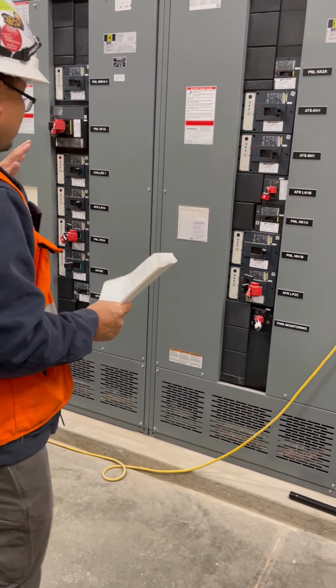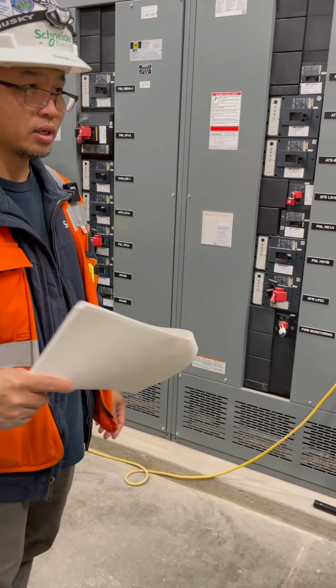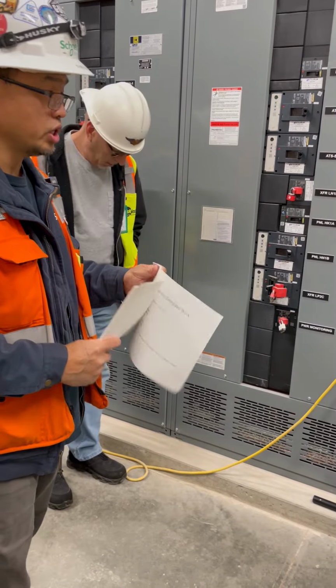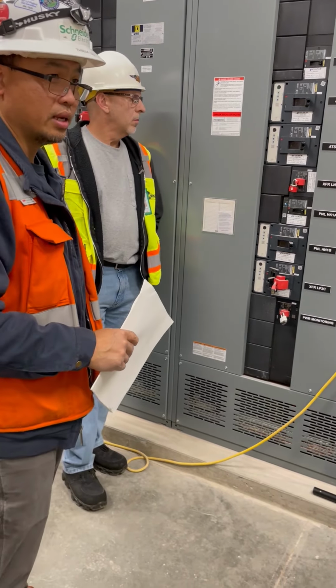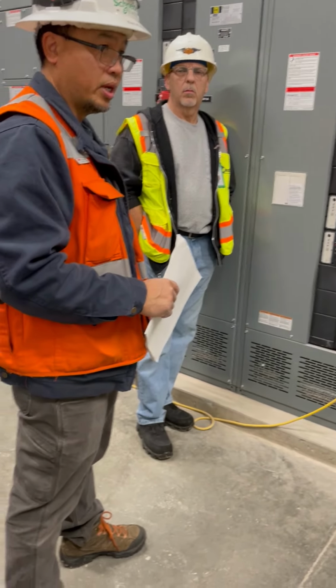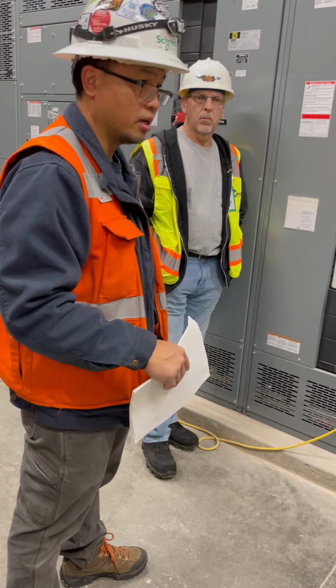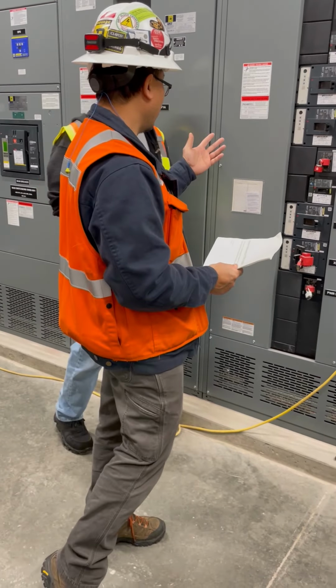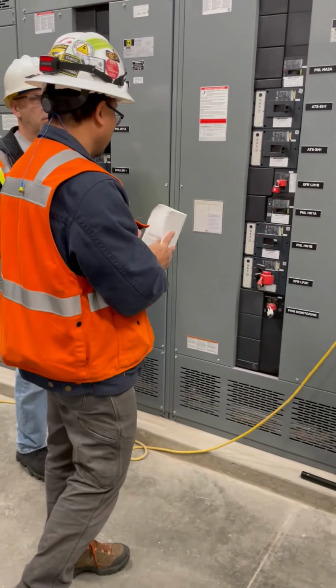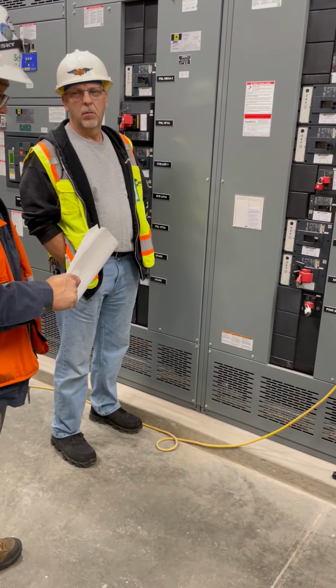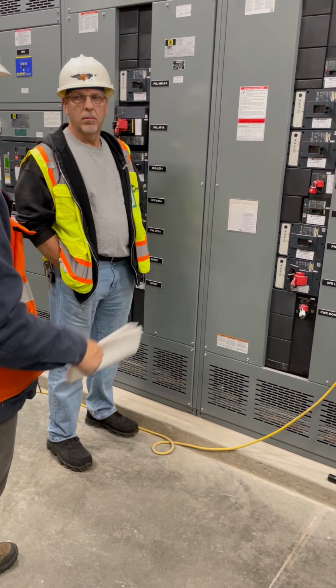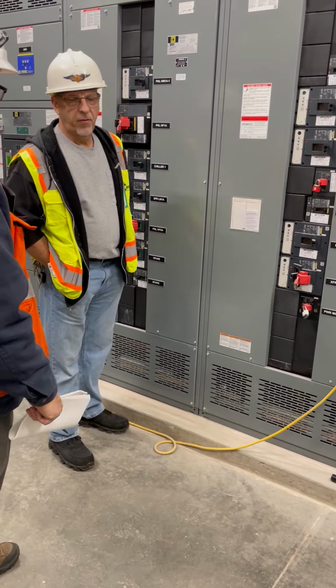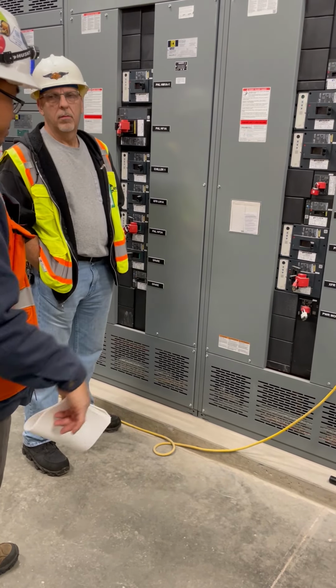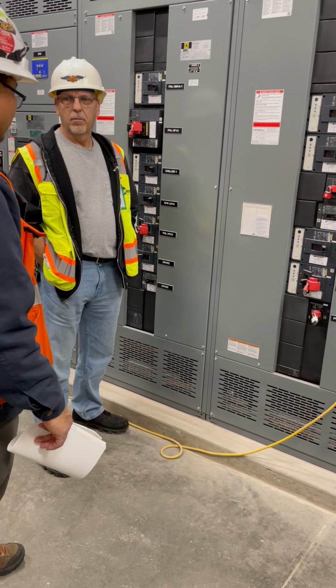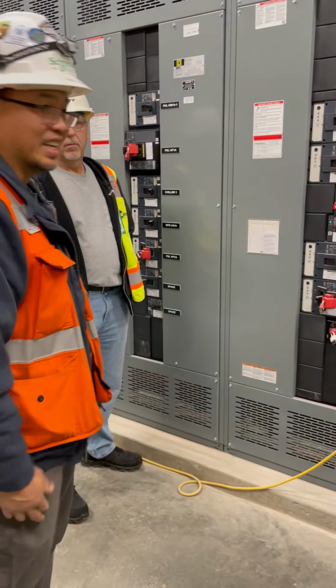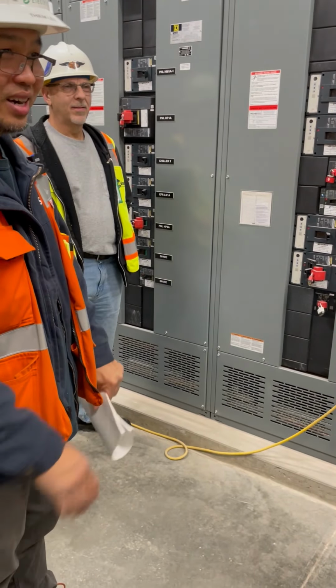You might think, well, I'm not going to be working on this in here, but if you have electricians come out and do work, you need to provide them this information, so they have the detail on what they need to wear to protect themselves. If the fault current is too high and the label says danger, prohibited, to ensure it can be worked on safely you have to de-energize the switchboard before you even open it up. I remember back then, I've been doing this for 25 years, there was no problem opening this and taking a look and sticking your head in there. We don't do that anymore.